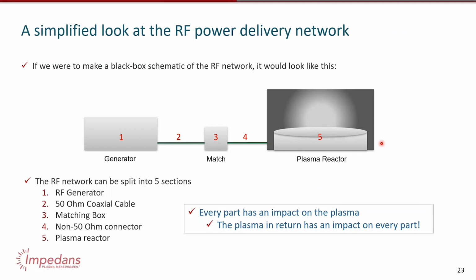And you can type in a report rate, so if you want data every 100 milliseconds or every 10 milliseconds, with the very latest probes that we sell, you can set that, and say you want data every 10 milliseconds on the reflected power, and have a close look at the ignition. I mentioned also that you can do arc detection.